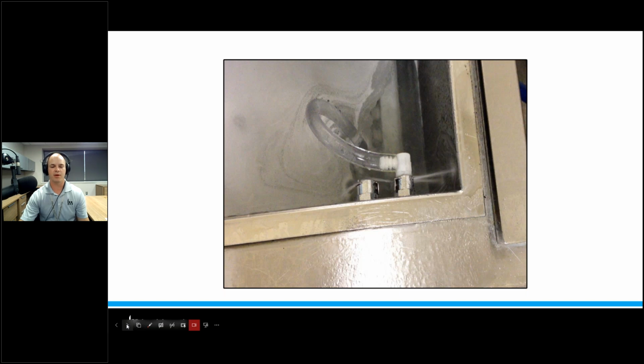A lot of times when we do these tests, we actually load one of our lumen cleaning tests and we don't hook it up to the lumen cleaning function, just so that you can see what happens inside the lumen when that flushing or cleaning mechanism is not used. As you can see in this particular case, it probably got some help from the enzymatic detergent, from soaking and all of that, but we definitely did not come up with an ideal cleaning result. So just something to be aware of in case that was on your mind because of how you use your equipment at your facility.